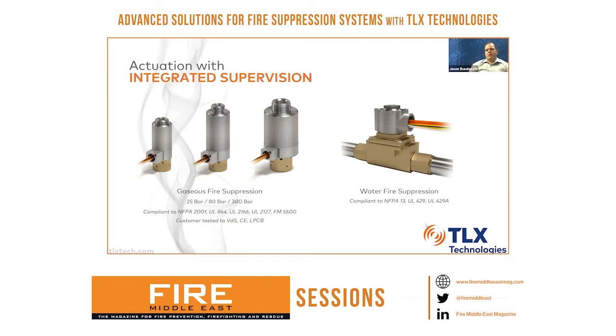As we've gone on through the years, gas fire suppression systems have really led the way with the installation supervision code under NFPA 2001, that is transferred over into NFPA 13 for pre-action and deluge systems and sprinkler systems. So as of January 1st, 2020, I'm sorry, NFPA 13 also adopted the installation supervision requirement that anytime one of these solenoid valve coils on pilot operated solenoid valves is removed, that same audible or visual signal needs to come from the control panel to let that personnel know that that device needs to be replaced appropriately.